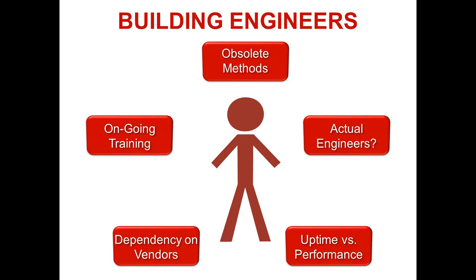In almost all of the facilities we work in, it is assumed that the building engineer is completely familiar with how everything works, and that is not the case. And although most building engineers do have a reasonable understanding and some background training in how to maintain the mechanical equipment in their facility, unfortunately their focus remains on uptime, and that goes back to that 50-year mentality of how buildings should operate. If we take a very, very close look at O&M tasking schedules for both contractors, vendors, controls contractors, and even the internal O&M staff, when we do reviews of those types of documents, we seldom see anything that has to do with energy performance-based tasking and activities.